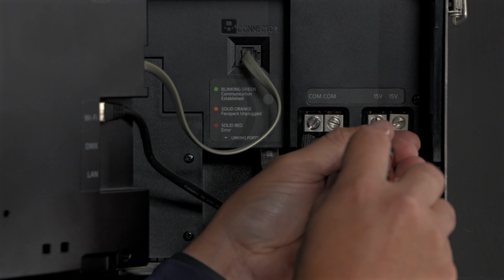The other overload, typically due to a miswired fixture, is when you have a short in the field. An overload short will usually trip the transformer immediately after startup. It'll try to turn on the lights, and then you will notice that the error message for an overload short appears right away. Once again, you can open the facepack and you'll see that the chassis LED is red. You will also be able to verify the overload and which chassis it is by pressing the home and back buttons simultaneously to get to the diagnostic screen. The overload field will be highlighted in orange.